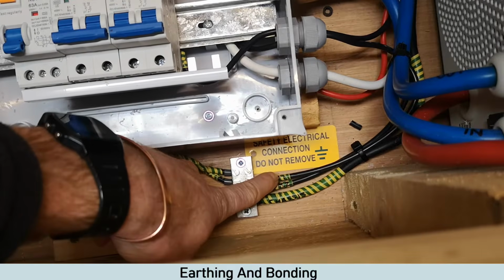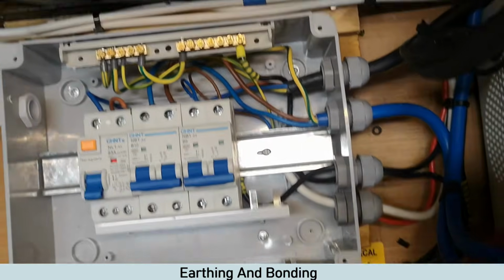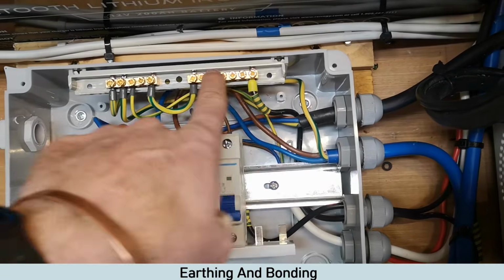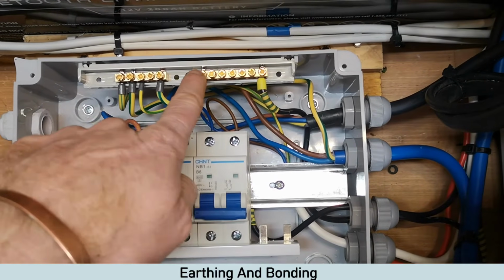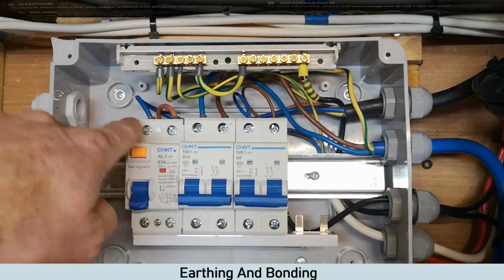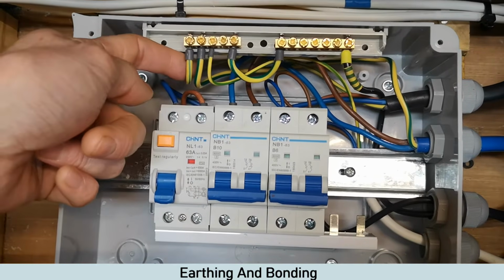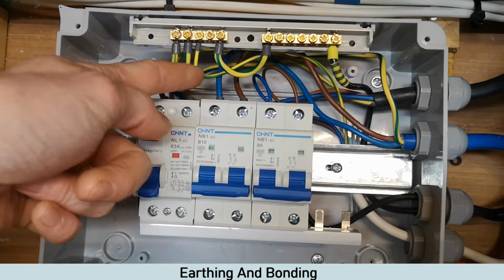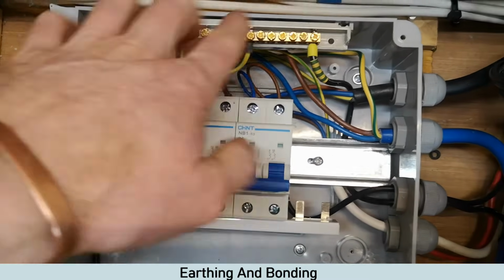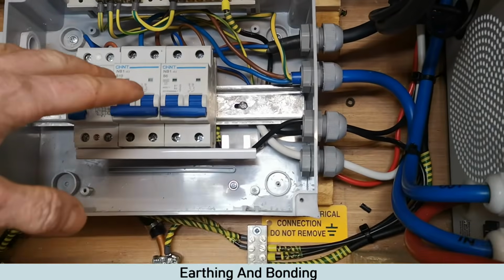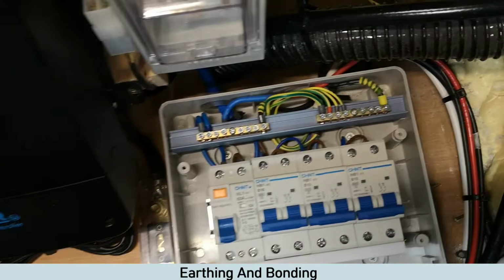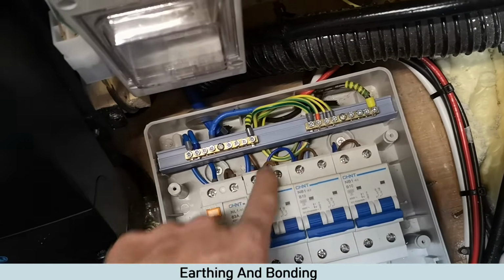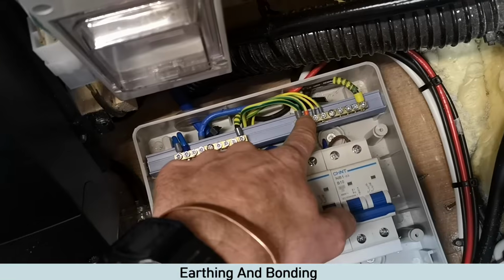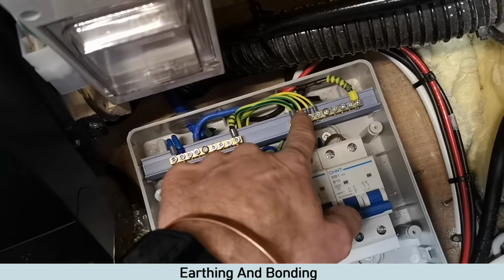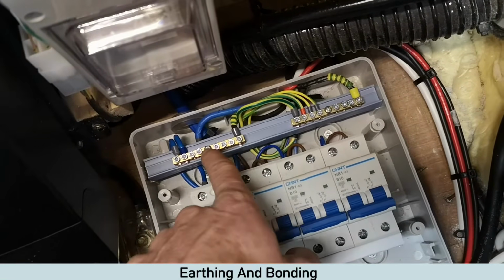So what we've also got is DB1 and DB2. One runs up to here, which goes onto our earth bus bar. We've got a link to this one. Then this is the hookup cable earth, then this is the inverter input, and then that's our fridge. So everything is linked together through there. And then the other one runs to DB2, which is here. Same again, we have the output earth and then each circuit in order, just running through there. That's our neutral bus bar, which I'll go into more depth in a bit.